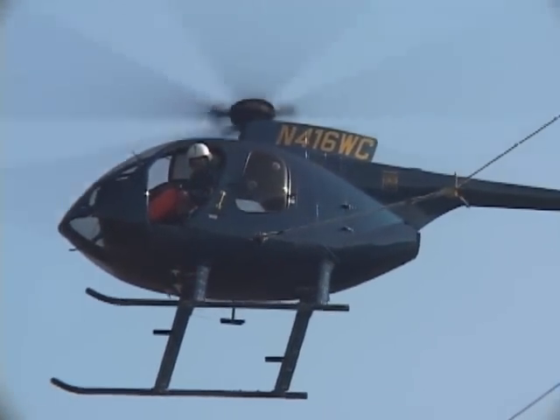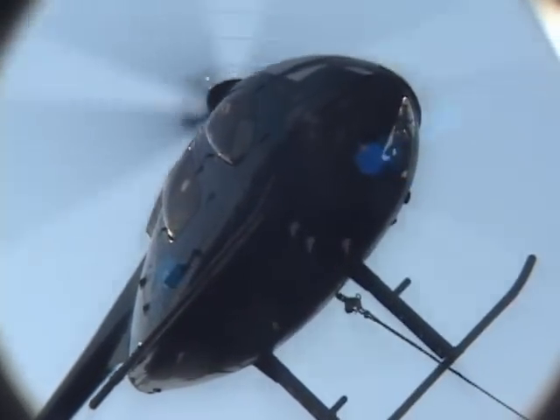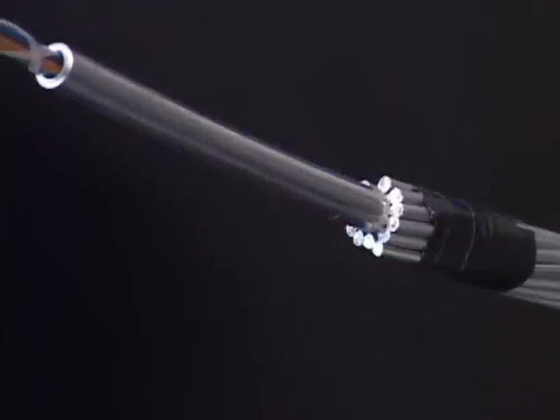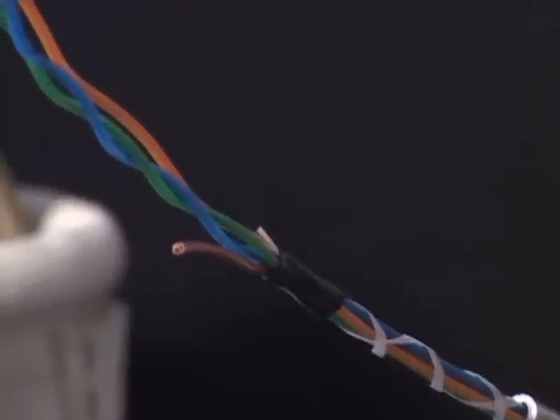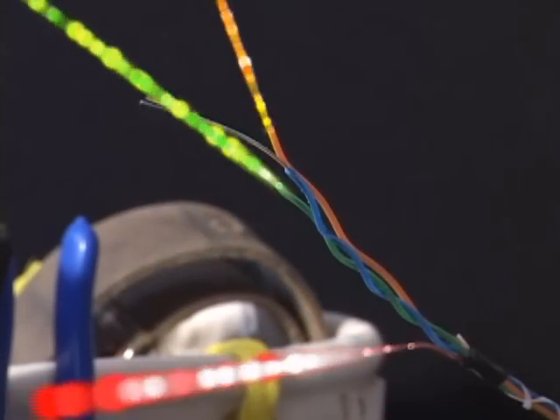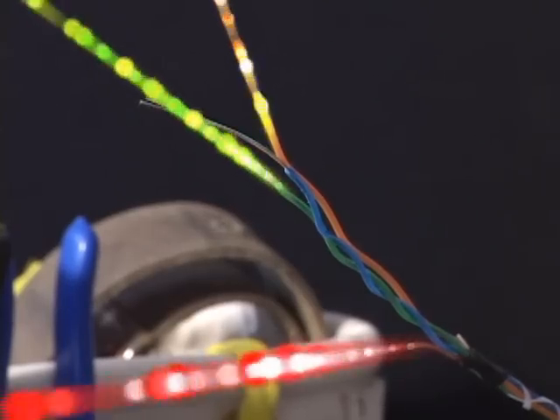The fiber itself is used for communication between system dispatch and substations and anything else that we may need for operational communication. The shield wire is smaller in diameter than conductor. An aluminum casing wraps around a steel one. Inside this protective and conductive exterior are 24 strands of fiber optic cable. Those fibers are the path through which our electronic devices communicate to ultimately keep electricity flowing to customers.